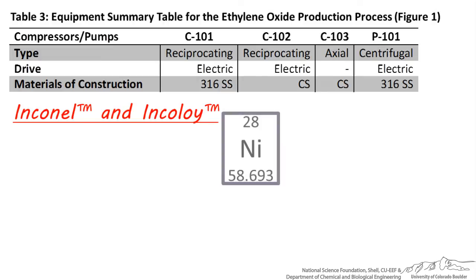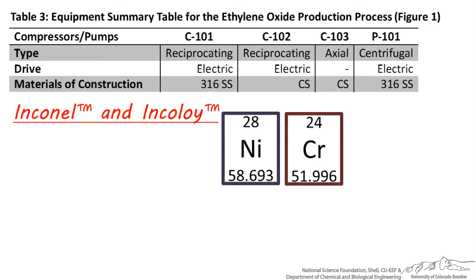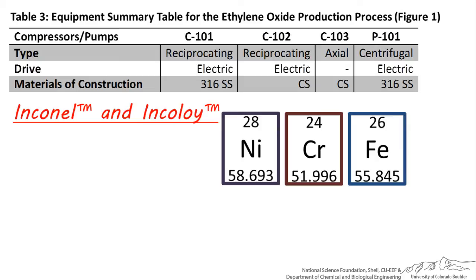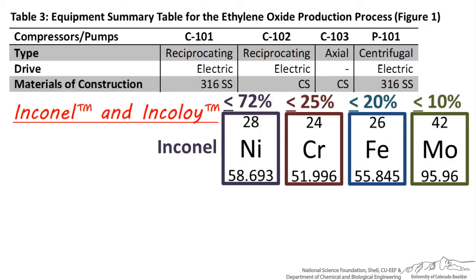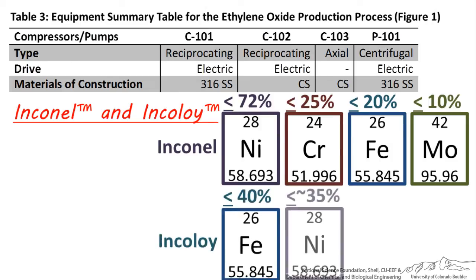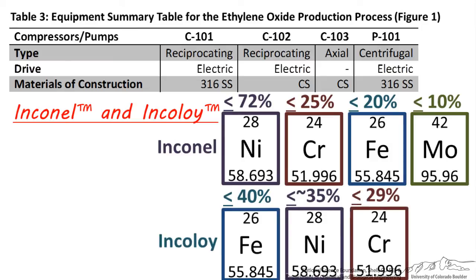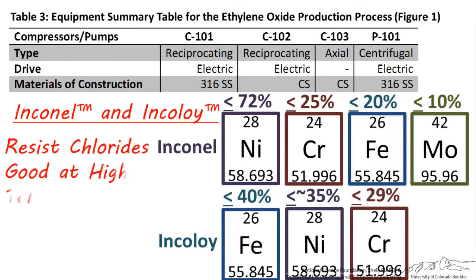Inconel and Incoloy are mostly nickel, with up to 30% chromium, as much as 40% iron, and up to 10% molybdenum, among other metals and nonmetals. The difference between them is that Inconel is up to 72% nickel, up to 25% chromium, and up to around 20% iron, while Incoloy has less nickel but more iron. Both Inconel and Incoloy are good to use at high temperatures and with chloride-containing chemicals.